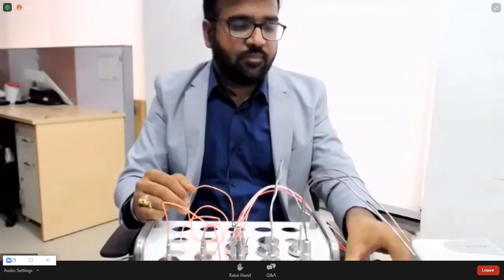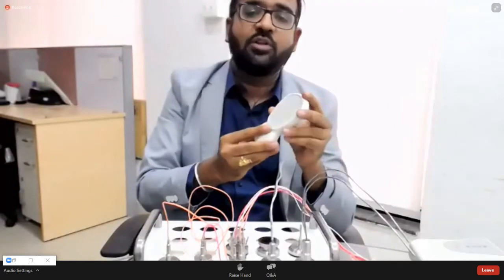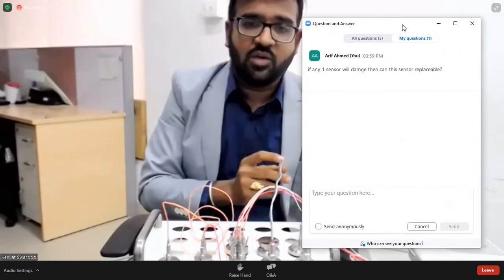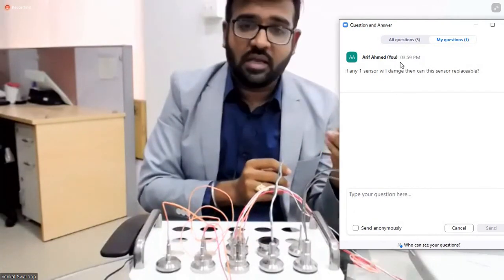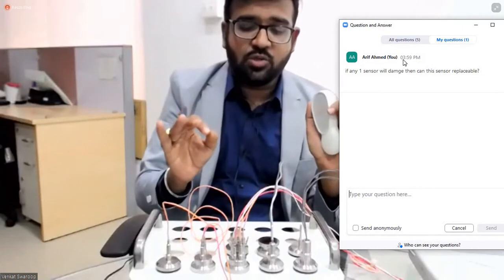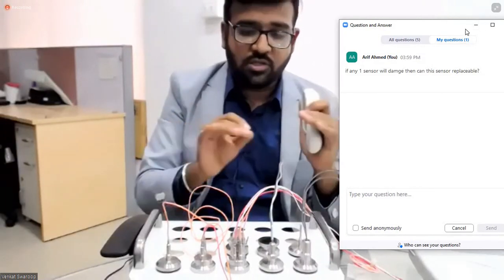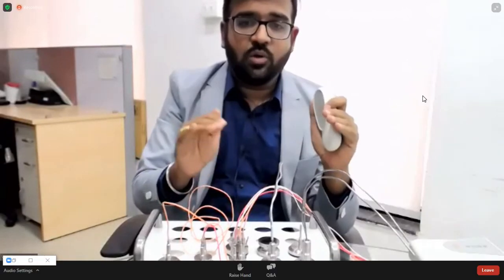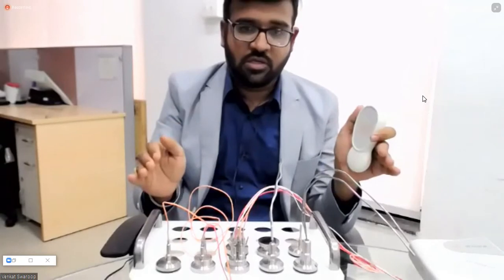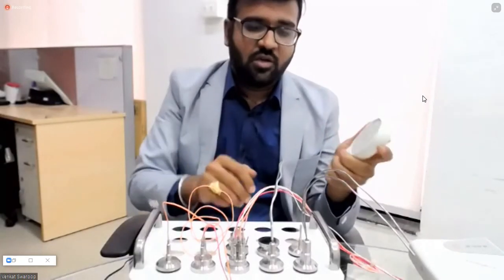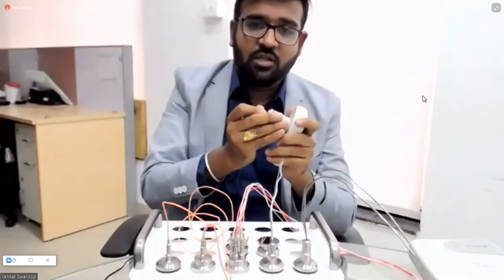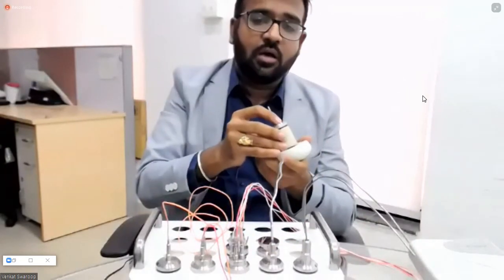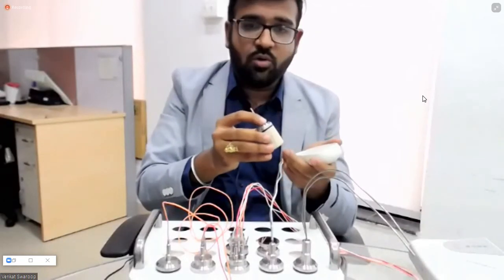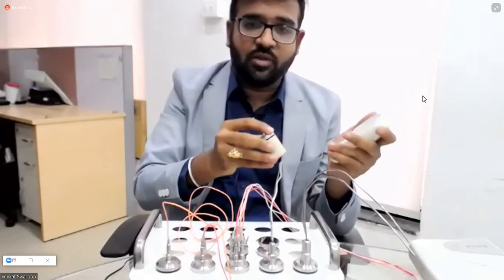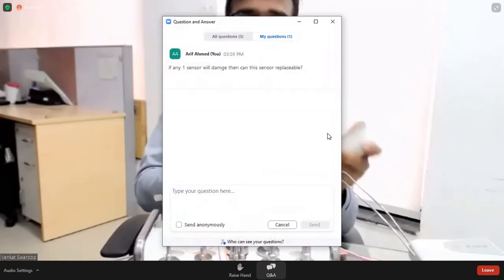Now I want to explain the magnetic wake-up device. As mentioned earlier, all loggers, when there is no job or program running, will go to sleep mode by default after 15 minutes. To wake up the logger, this is a special device. When you bring the logger in contact with this device, the logger will wake up and you'll get a beep sound at the base station. Along with the sound, you can also see a status LED symbol on the base station, so you can understand that your logger is in the switch-on position. So this is about the magnetic wake-up device.